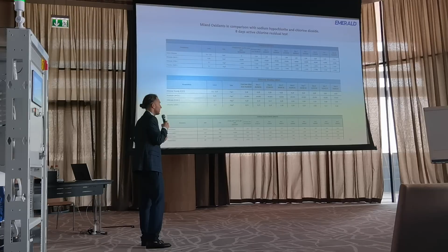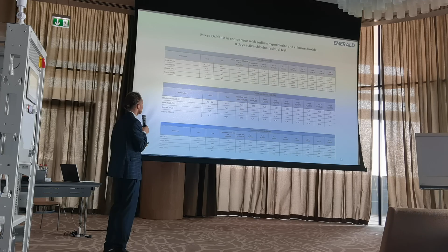With sodium hypochlorite, the active chlorine was similar, around 135, degrading at a similar rate, but you can see bromate formation happening, and chlorate formation also happening. So for now, it seems like the only solution not giving any of the key disinfection byproducts for the Middle East is mixed oxidants, and this was proven.